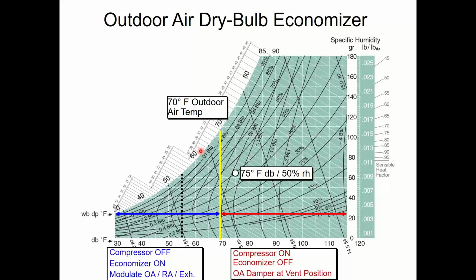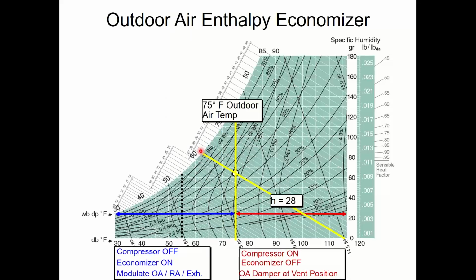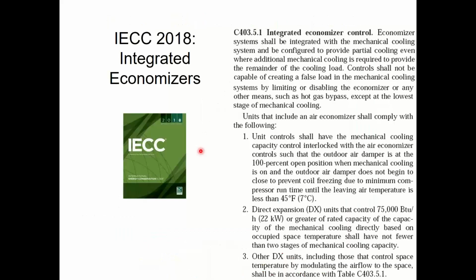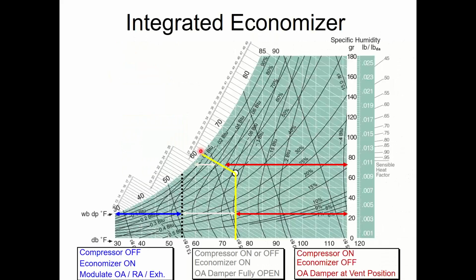I'm not saying you should do that. I'm just saying if you pick the wrong economizer control and you do dry bulb, you're going to end up going back and either putting an enthalpy sensor in or cheating the code. One of the two. The code also requires you to have an integrated economizer. What does that mean? That means you have to run the compressor in conjunction with the economizer when it's appropriate.